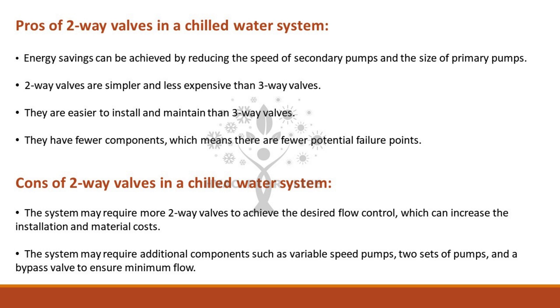Cons of two-way valves in a chilled water system: the system may require more two-way valves to achieve the desired flow control, which can increase installation and material costs. The system may also require additional components such as variable speed pumps, sets of pumps, and a bypass valve to ensure minimum flow.